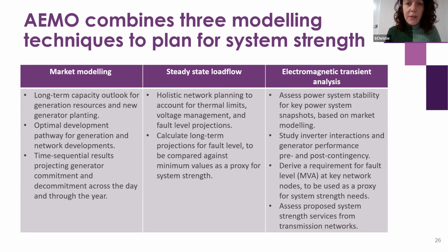Secondly, we do steady state load flow. That is, of course, part of the traditional thermal and voltage limit planning for transmission networks. We do that to look holistically at what is happening in the system, look at thermal limits, voltage management. We also pull some fault level projections out of that.